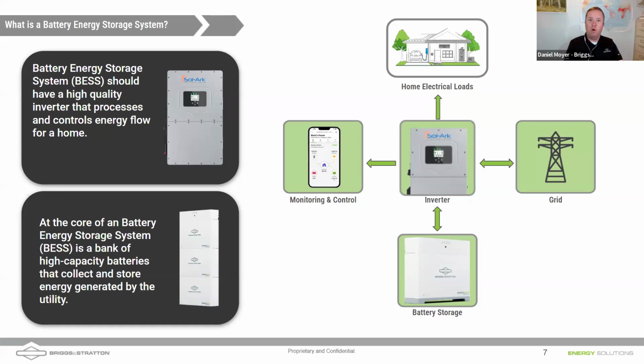You put it all into one box, that hybrid inverter right there. That's also where the transfer switch is, although we call it an MID. What will happen is that if the Sol-Ark detects a loss of grid, it will disconnect from the grid within milliseconds. A lot of times homeowners don't even notice that the loss of grid has occurred. Maybe they might see the lights flicker for a millisecond, or look out the window and see that the neighborhood is dark, or look at their app and see that they're in an off-grid mode.